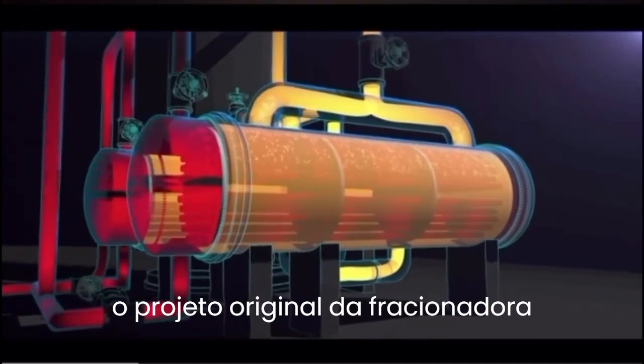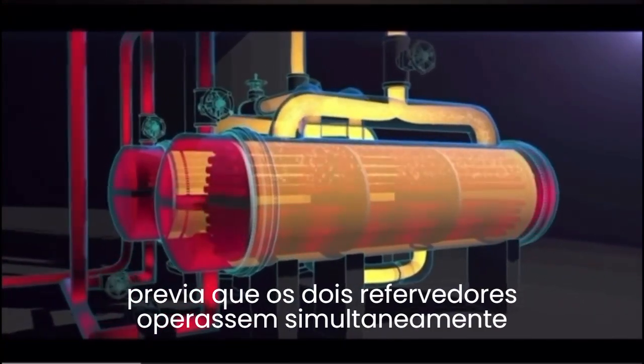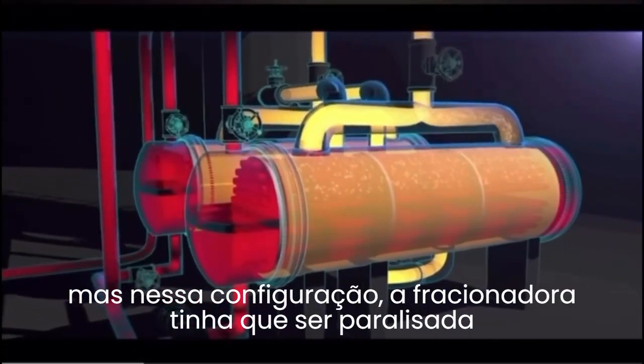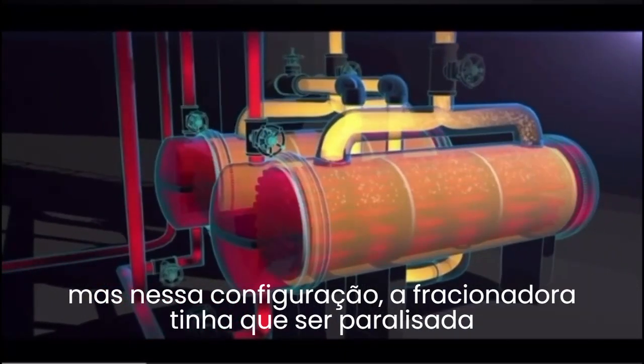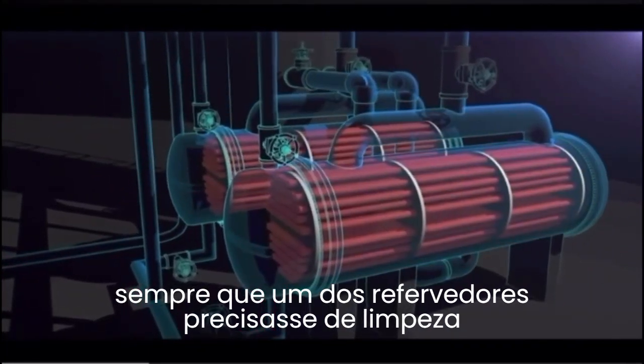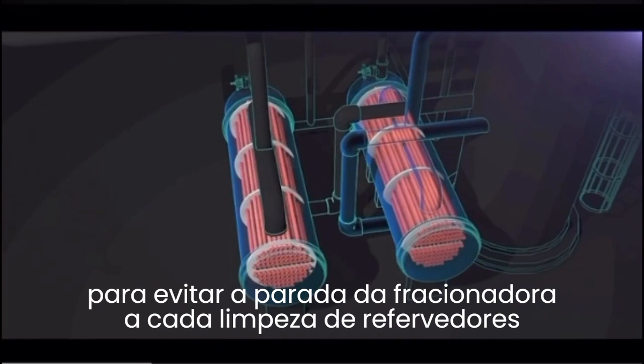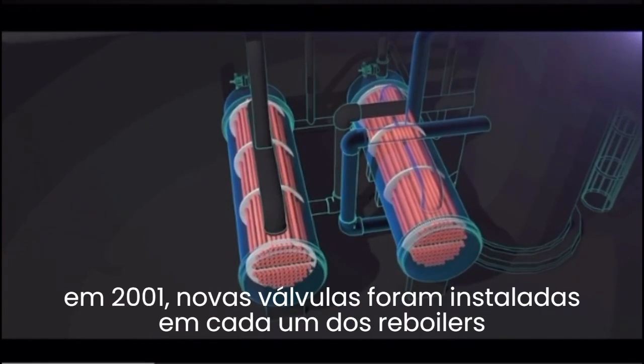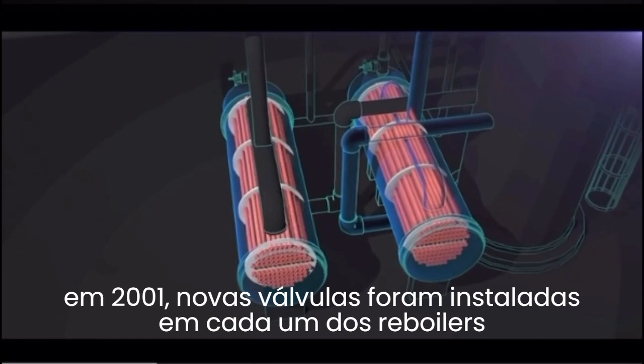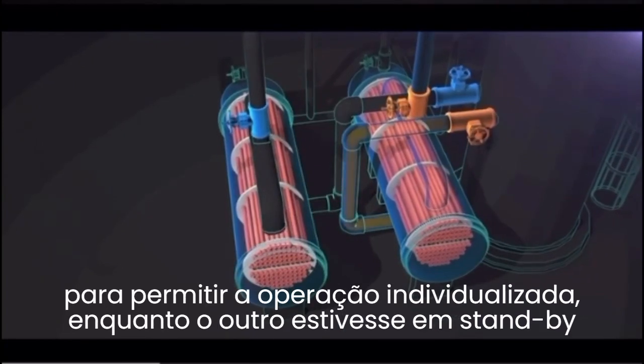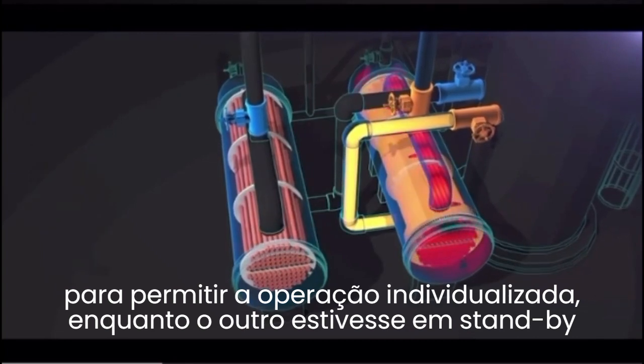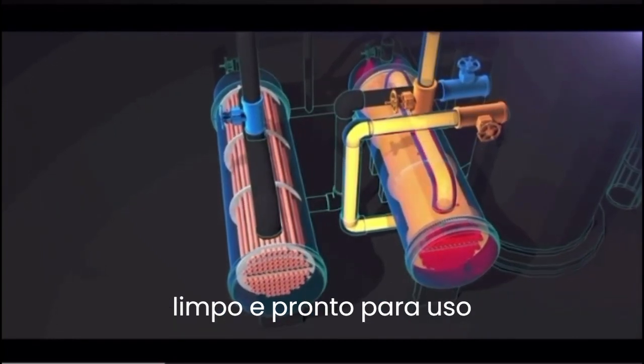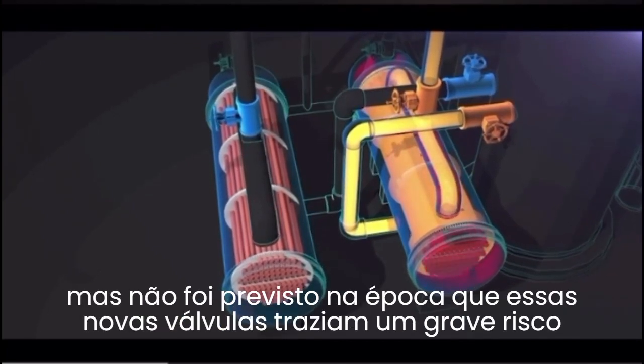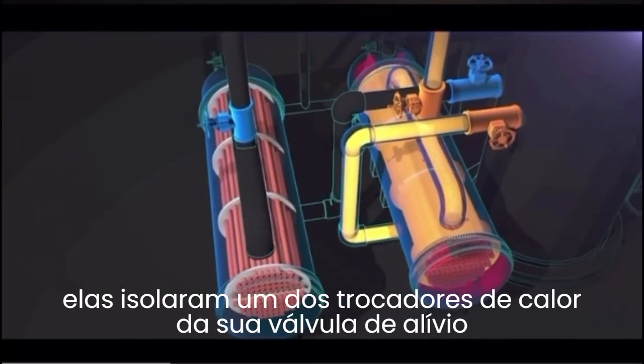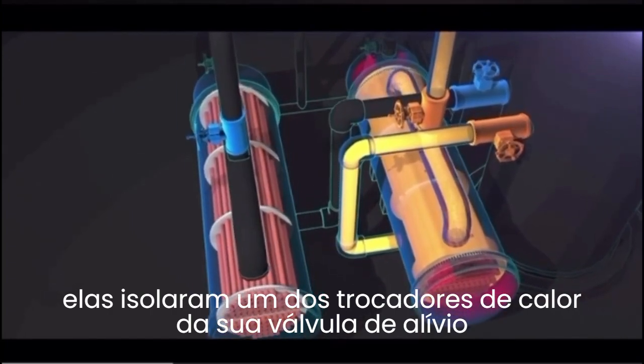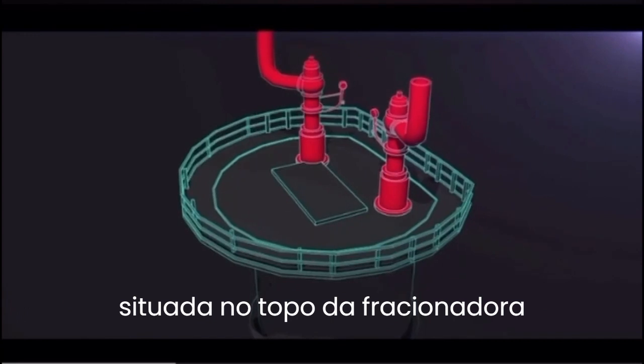The original propylene fractionator design had both reboilers running simultaneously. But in that configuration, the fractionator had to be shut down when a reboiler fouled and needed cleaning. To prevent shutdown of the propylene fractionator each time the reboilers needed to be cleaned, in 2001, new valves were installed on each reboiler to allow for operation of only one at a time. The other reboiler is on standby, clean and ready for use. But unforeseen at the time, these valves introduced a serious hazard. They isolated the standby reboiler from its protective pressure relief valve, located on top of the fractionator.